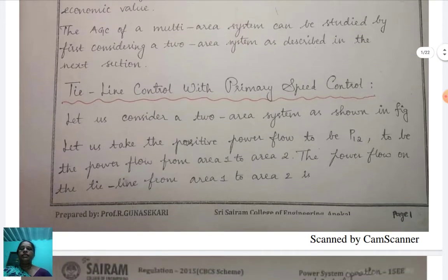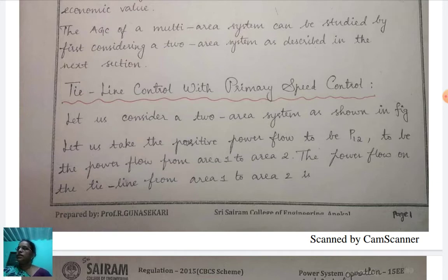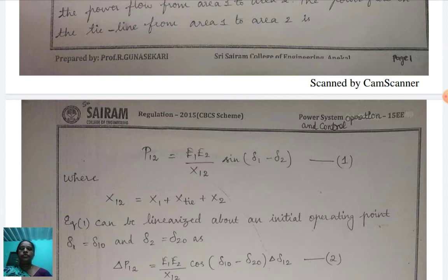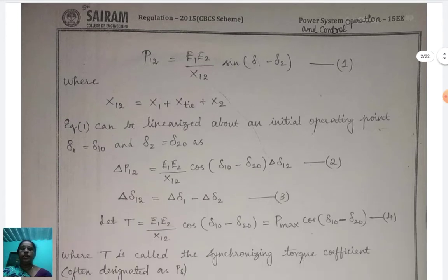The first topic is Tie Line Control with Primary Speed Control. Under this topic, we study the change of load in area 1, change of load in area 2, and change of load in both areas. First, we study P12, which is the power interchange from area 1 to area 2. That is equal to (E1 × E2) / X12 × sin(δ1 − δ2), where X12 = X1 + X_tie + X2.